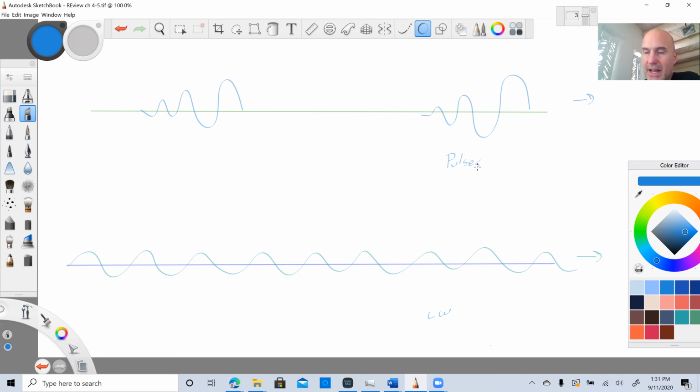There are situations where that happens, but in the most basic of ultrasounds, it does not happen that way. One pulse, all the echoes, then the next pulse. This listening time from here to here is greatly increased when you go deep into the body. Deep in the body, you have to wait longer for all the echoes. So you have to listen longer. It makes perfect sense.